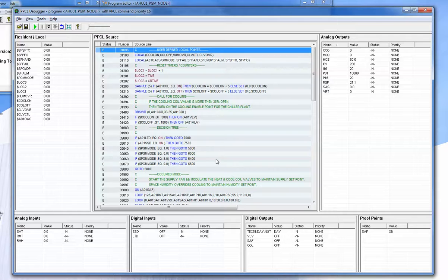First, an overview in general about the PPCL debugger. First, there's no impact to the running system or equipment. Nothing else is required. The PPCL debugger is actually a subset of the entire firmware, so it doesn't work 100% the same as it would with online firmware running.